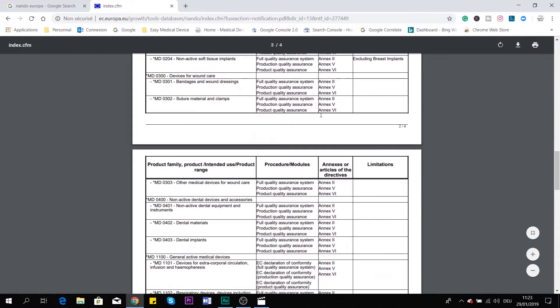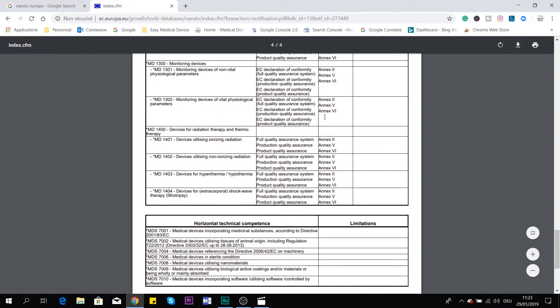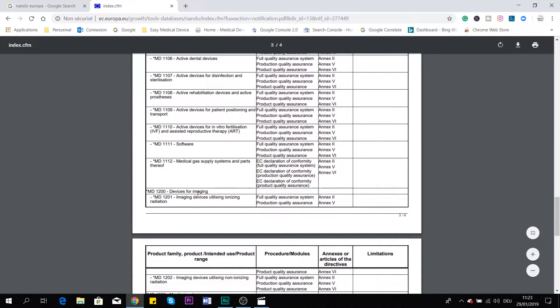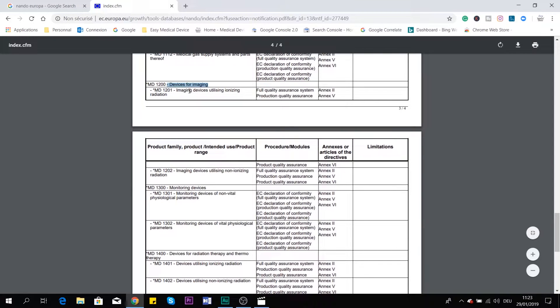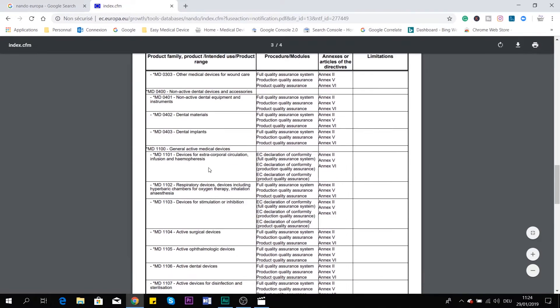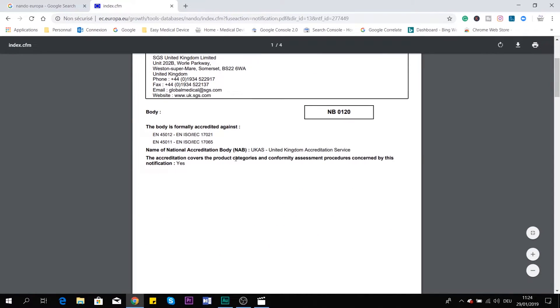It's a big list, but if you have a specific product, you have to check it. For example, if your product is a device for imaging, you can check whether this notified body is accredited for that — and you can go more specifically: is it imaging devices utilizing radiation, et cetera. So when you are looking for a notified body, you also have to check which products that notified body is accredited for. The notified body should tell you yes or no — I am capable to certify you for this product.